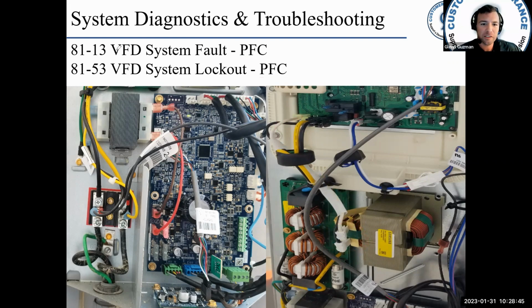After 2 occurrences of the 8113, you will get the 8153 and lock out for 4 hours. A power cycle will clear the malfunction timer, but continued malfunctions indicate a high current situation. Okay. You could have VFD or compressor damage. You could have reactor damage. Measure the resistance of the reactor. If the measurement is OL, meaning open, then replace the reactor. Otherwise, replace the VFD. The reactor resistance should be low, but if you're reading OL, then replace the reactor.